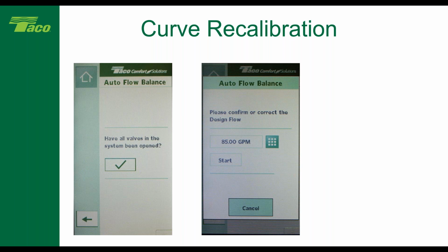When I enter autoflow balance mode, I'm going to program in, and it's already going to have it known as what the design flow is. You're going to open all the control valves in the system, and the pump's going to ramp up, and it's going to figure out what the maximum head is at that design flow, because it's going to come up until it hits the design flow. So let's say it's 1,000 GPM, and you designed it for 100 feet of head, but it was able to hit design flow at only 85 feet of head.